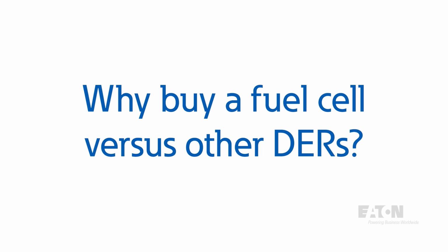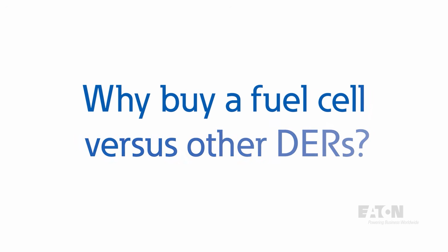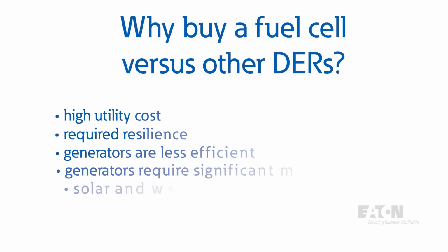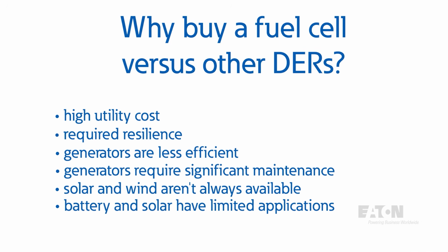So why buy a fuel cell versus a more traditional power source? Fuel cells offer unique advantages over traditional power sources. Utilities are generally the lowest cost energy source, but in some areas utility costs can be very high. In addition, resilience and availability are a concern for sensitive loads. As a comparison to natural gas generators, generators burn fuel and are much less efficient. Since they require a rotating machine, they may also require significant maintenance.